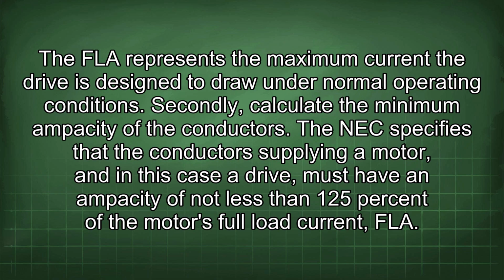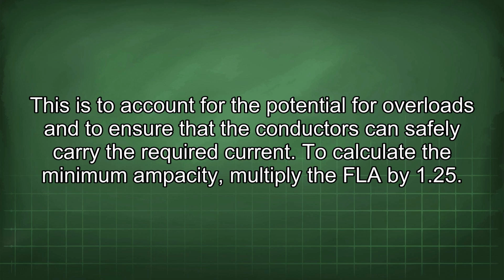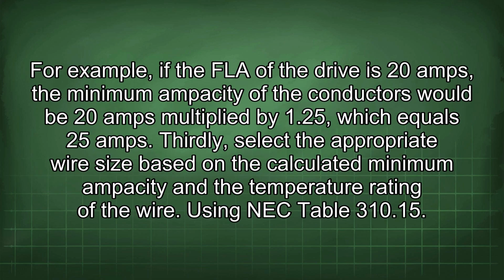Secondly, calculate the minimum ampacity of the conductors. The NEC specifies that the conductors supplying a motor, and in this case a drive, must have an ampacity of not less than 125% of the motor's full load current (FLA). This is to account for the potential for overloads and to ensure that the conductors can safely carry the required current. To calculate the minimum ampacity, multiply the FLA by 1.25. For example, if the FLA of the drive is 20 amps, the minimum ampacity of the conductors would be 20 amps multiplied by 1.25, which equals 25 amps.